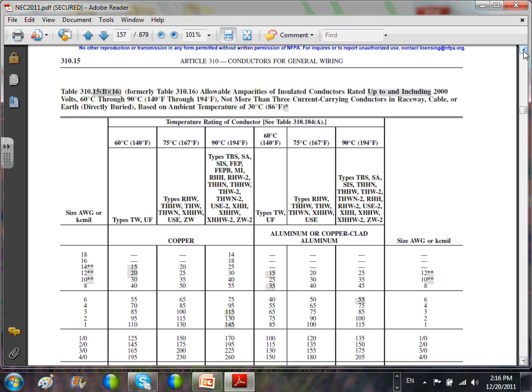it becomes continuous. So say I have a 10 amp motor and I need to size a cable for it. 10 times 1.25, right? That'll give you 12 and a half. Motors, the terminals on the lugs of the motors, that's going to be on your master exam annual journal when you sit there. No question asked. The terminals on the motors, as well as the circuit breaker, the lug terminals where you tie the conductor, are rated for 75.